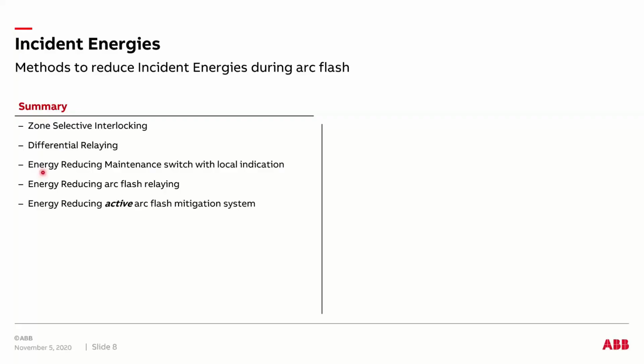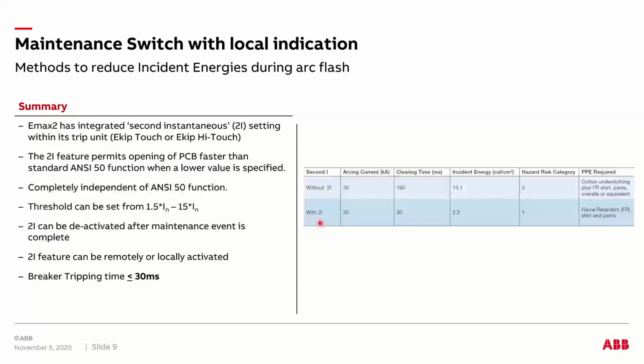It is a setting on all our low voltage breakers, whether it's AVB, Emax2 breakers, or the legacy GE low voltage breakers. It comes with a local indication, where when you have an operator standing in front of an equipment, you can activate that reduced energy let through switch, and it switches over to a second instantaneous. We call it 2I, and when the 2I second instantaneous is activated, you have a really fast clearing time of about 30 milliseconds, which is roughly 2 cycles, when there is an arc flash event that occurs.